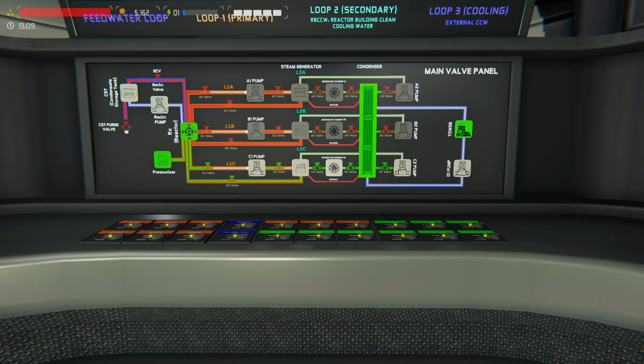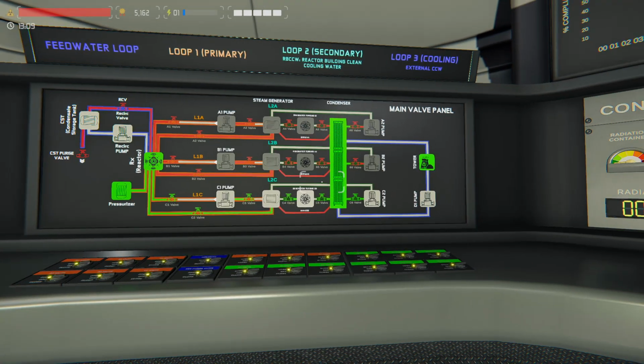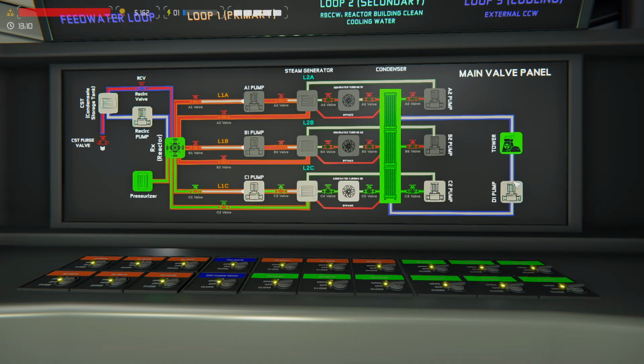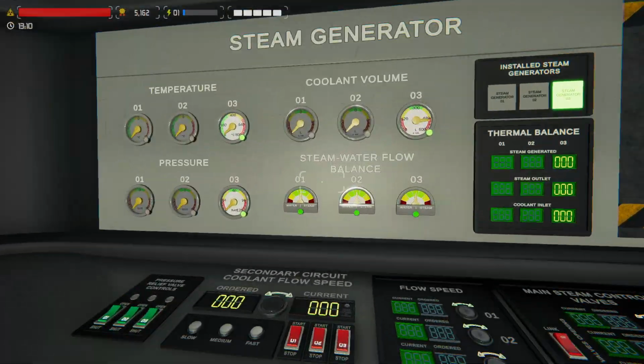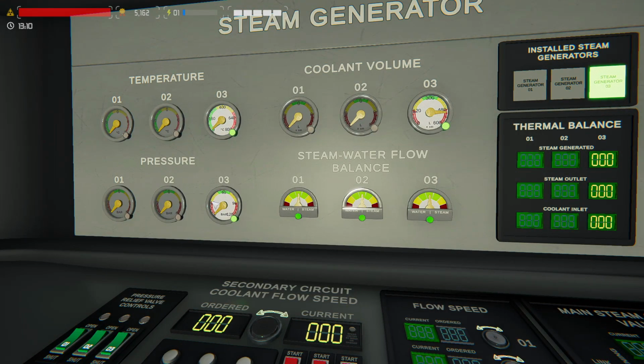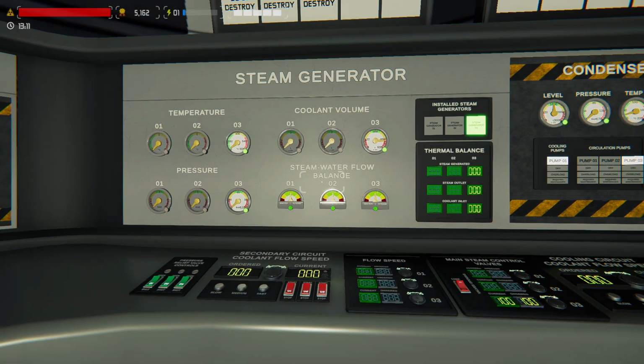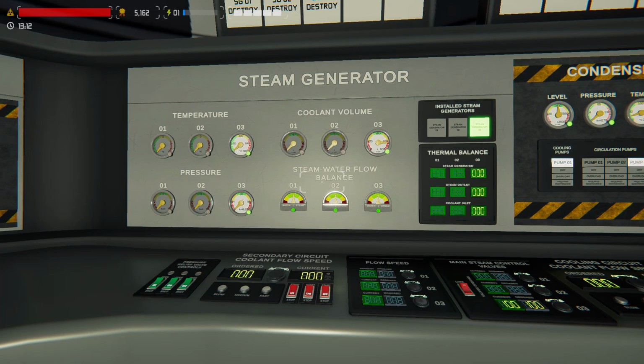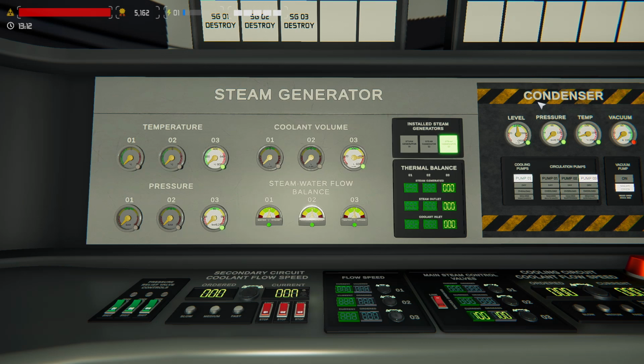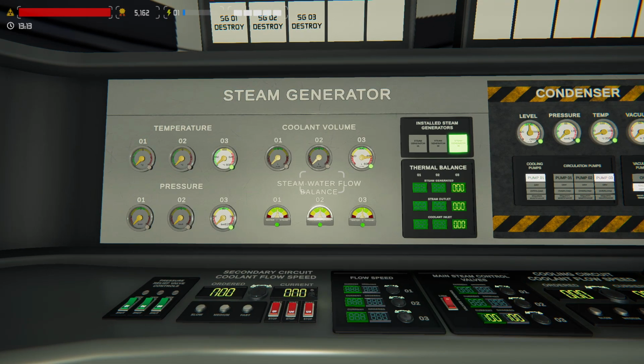Are you going to use that as you're going throughout this, like your gameplay minute by minute? No, absolutely not. But it's important to know, because as you understand how these concepts work together, you can diagnose issues: why is my temperature rising but my pressure falling? Those two should be in lockstep, as one goes up the other should go up. Why is this rising? They should never all three rise. As you see these things happen you can think it through: okay, my pump is dumping cold water from my condenser, which is causing this to raise, which causes the temperature to come down, which means I'm generating less steam, which means my pressure is going to fall, which is why I'm seeing my steam generation go down. That's why I'm telling you all this, so you can apply these concepts to your own game as you play it.